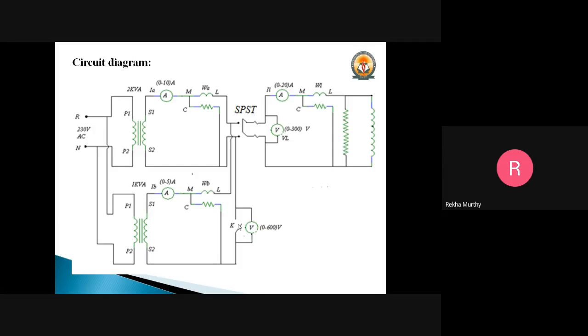The no load reading will be noted down. When the voltmeter reads 0, the SPST switch K1 is closed, and we note down the no load readings. Loading will be continued in steps of 2 amperes by varying both the resistive and the reactive loads. It should be taken in such a way that the ammeter connected to the secondary does not exceed the rated current of the corresponding transformer.